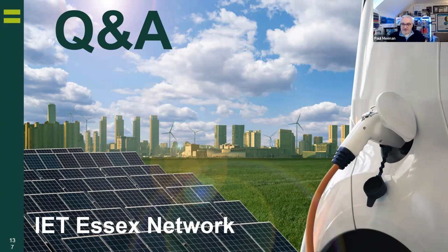If you, Carl, can type some more in there, that would be great to understand your mindset on that. But as far as I'm concerned, is RCD protection still required? Yes, just make sure it's the right type. If you have a motor connected, is it purely resistive, or one of the new electronic types? Do you need a Type A on it? Those are questions to ask the manufacturers. But for me, RCD protection on the roller shutter is a given, absolutely.